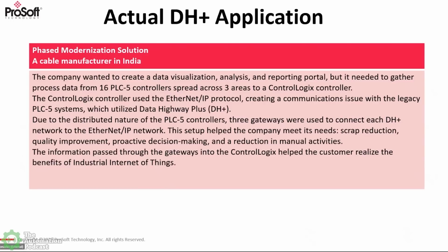In the first case, the customer wanted to pull data from 16 PLC5 processors and send that information to a Control Logix via Ethernet IP protocol. The issue was the communication between the two processors. The Control Logix is an Ethernet-based controller, while the PLC5 only communicates using serial, either DH Plus or Remote IO.